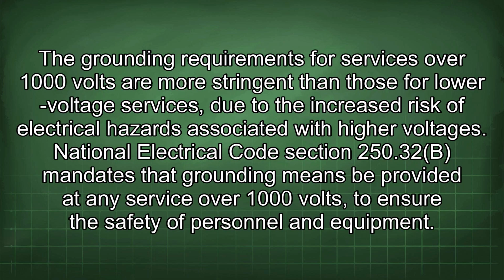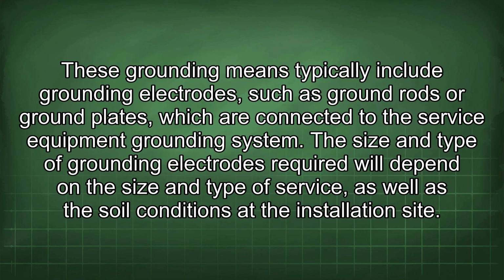The grounding requirements for services over 1000 volts are more stringent than those for low voltage services, due to the increased risk of electrical hazards associated with higher voltages. National Electrical Code Section 250.32(B) mandates that grounding means be provided at any service over 1000 volts to ensure the safety of personnel and equipment. These grounding means typically include grounding electrodes, such as ground rods or ground plates, which are connected to the service equipment grounding system. The size and type of grounding electrodes required will depend on the size and type of service, as well as the soil conditions at the installation site.